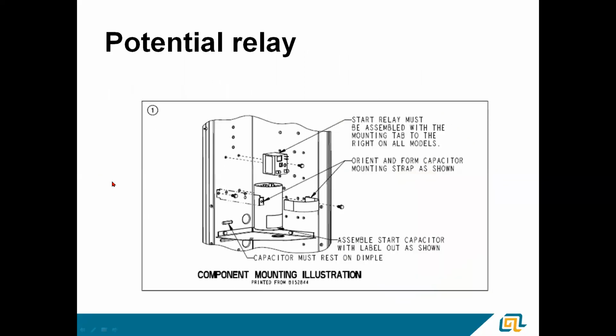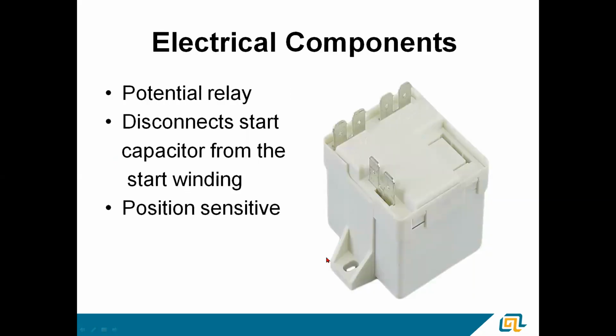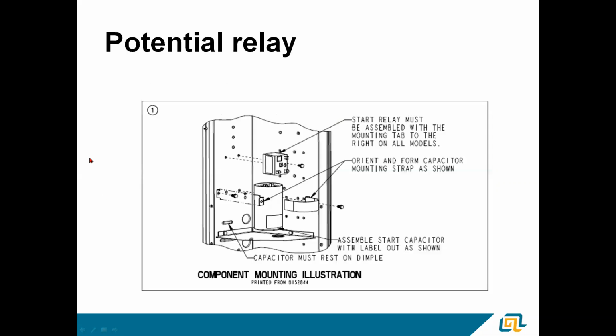In Trane American Standard equipment, the tab on the unit will always point right. I'm gonna pop back to that other slide. The mounting tab right here should always point to the right when it's installed. So just so you know, this is an illustration right out of the installer's guide for a start assist kit, and you can see the start assembly always has the tab to the right.